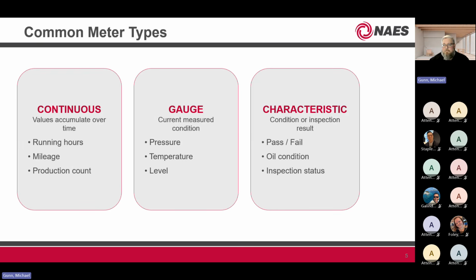The different types of meters in Maximo: first, continuous. These accumulate over time — key examples are run hours and mileage. As you check mileage on your cars or run hours on your turbines weekly or monthly, those populate and accumulate over time until you reach your 10K, 20K, or whatever maintenance threshold. The other type is gauge, which is exactly how it sounds — you can capture information for pressure, temperature, and level.